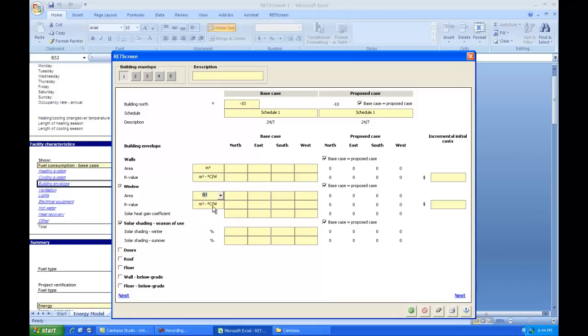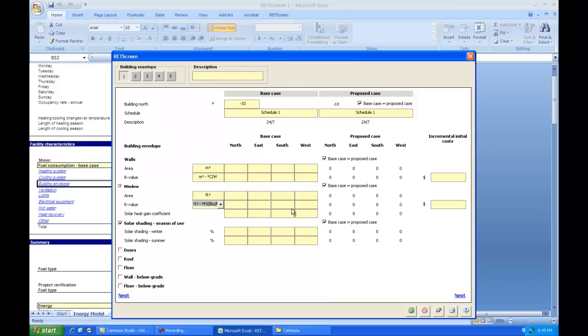The R value then we get to choose from one of four things here. The first one is a metric R value. The second one is an imperial R value. The last two are U values. U is the inverse of R. I'm going to work with imperial R values today. We'll talk later about how to actually get the numbers that go in here. But obviously it will be the area of your windows paying attention to which ones face in which direction, and then the R value associated with each one of those windows.